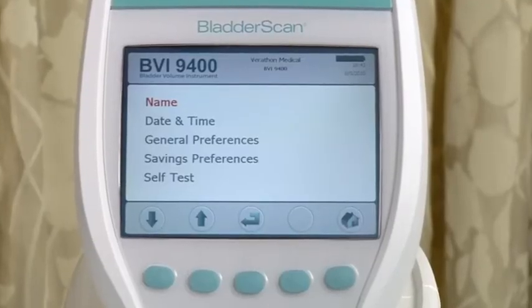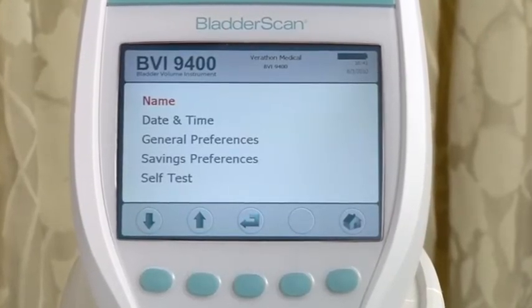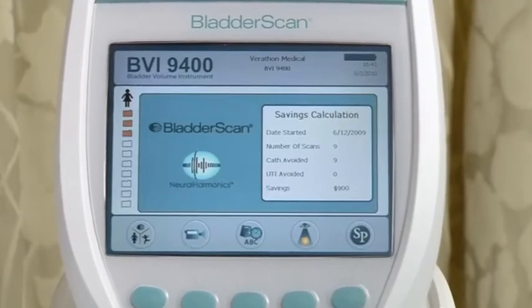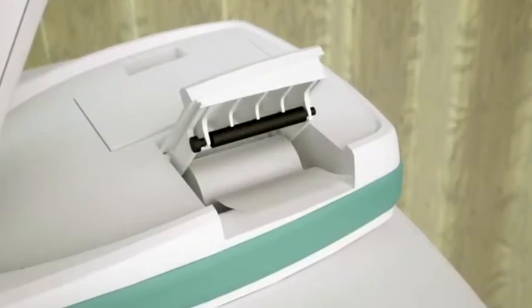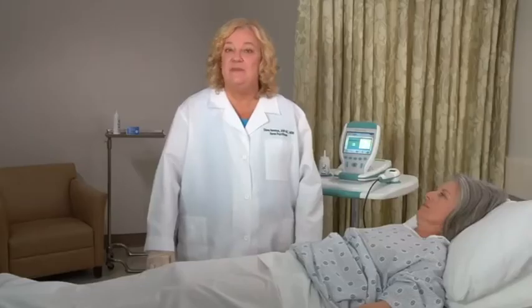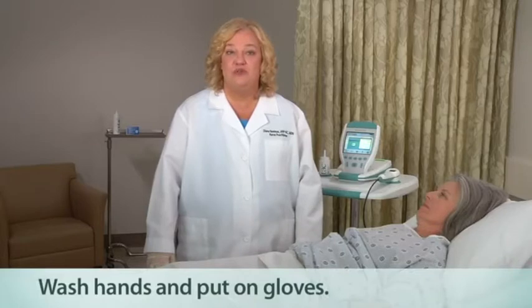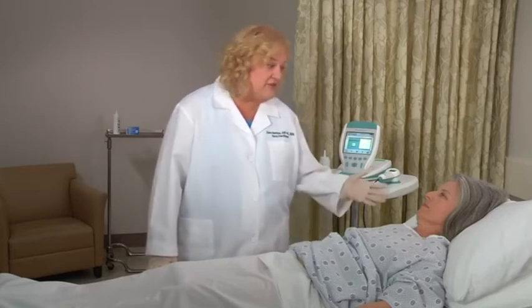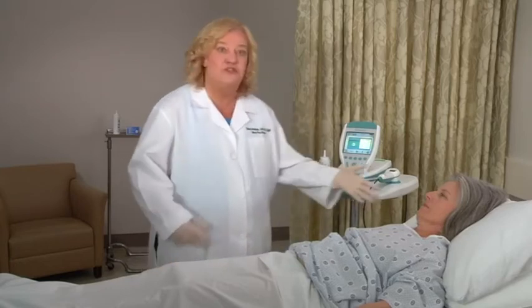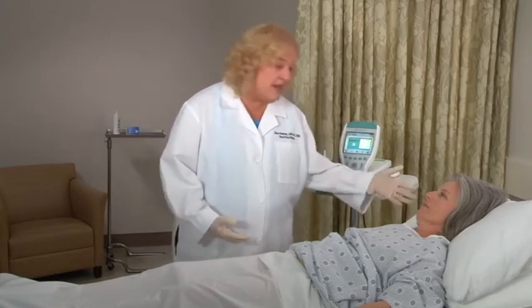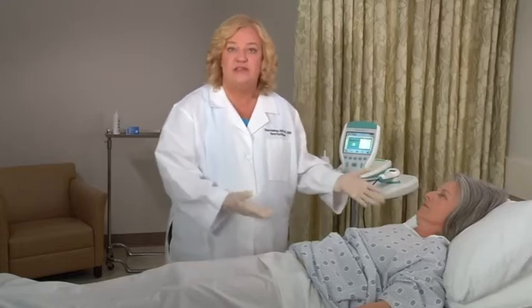Also, before using the BladderScan, personalize the instrument with the name of your practice and the correct time and date, as this information will be shown on all printouts. Check to make sure the battery is charged and there is enough paper in the printer before you start to scan a patient. If the patient is being scanned for post-void residual or PVR determination, it is important that the patient urinate before doing the test. Explain to the patient the BladderScan procedure and the reason for measuring bladder volume. Have the patient lie in the supine position, flat with head elevated on a pillow. Like this would be really the best position.